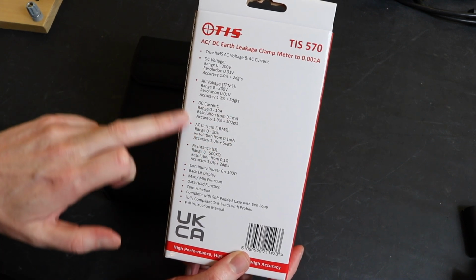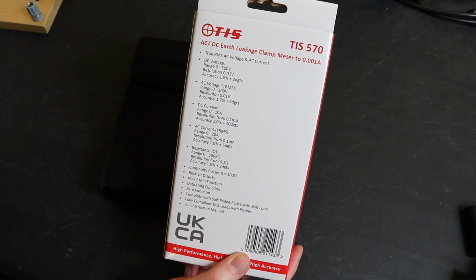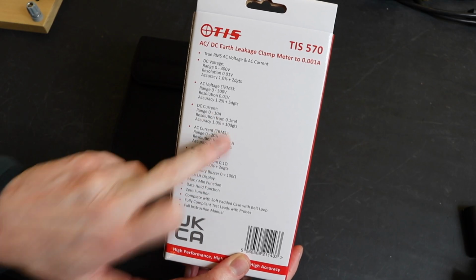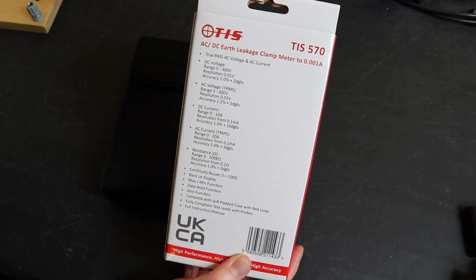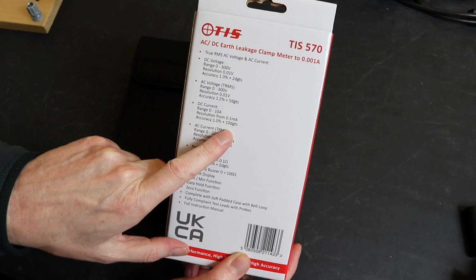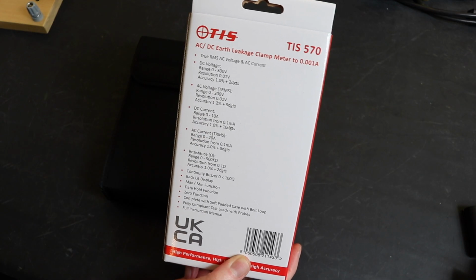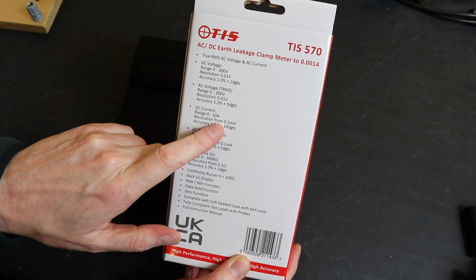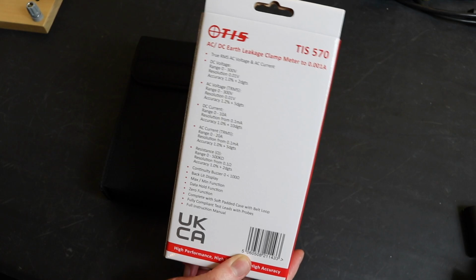One we're interested in here predominantly is this DC current, 0 to 10 amps, but with a resolution of 0.1 milliamps. However, we do have an accuracy of 1% plus 10 digits, so that 10 digits already puts us into plus or minus 1 milliamp accuracy level there.